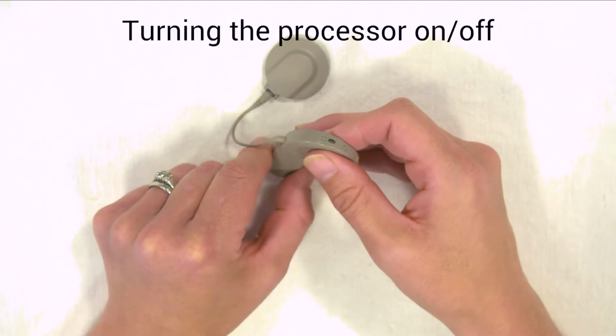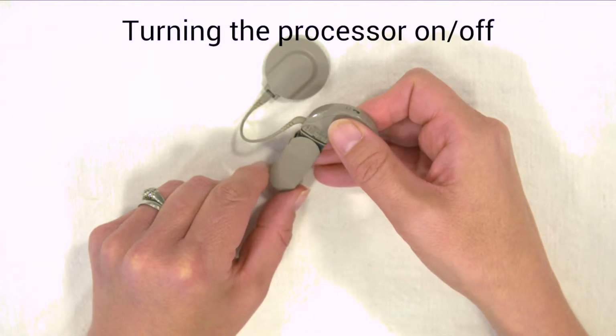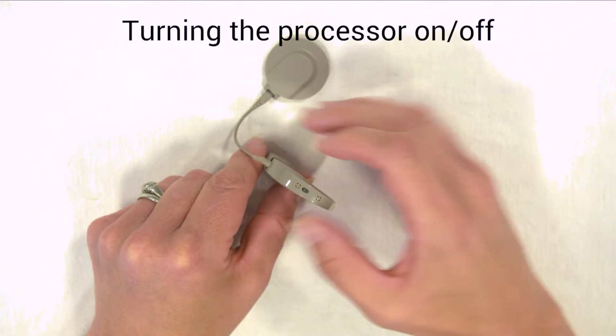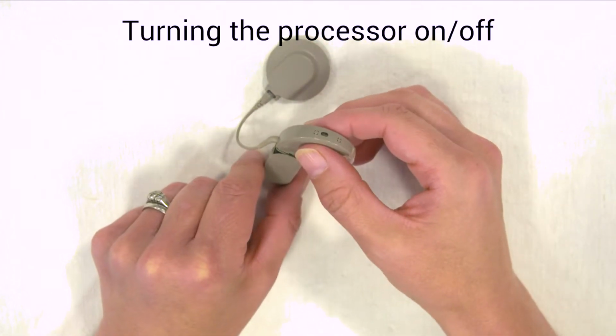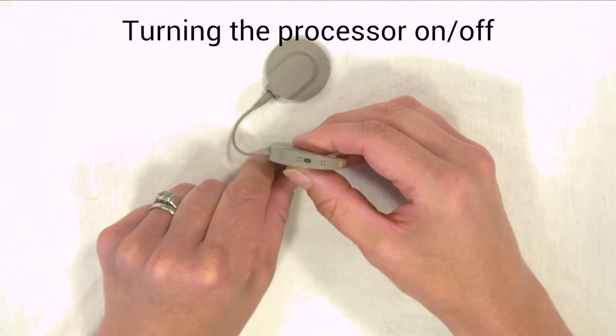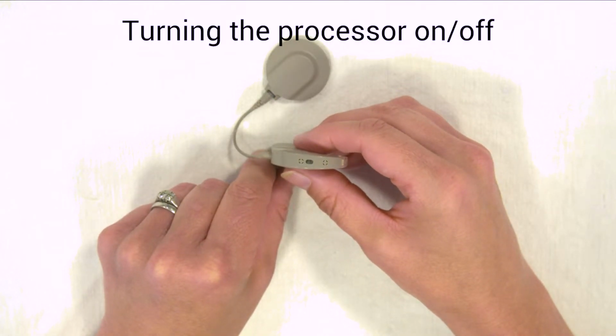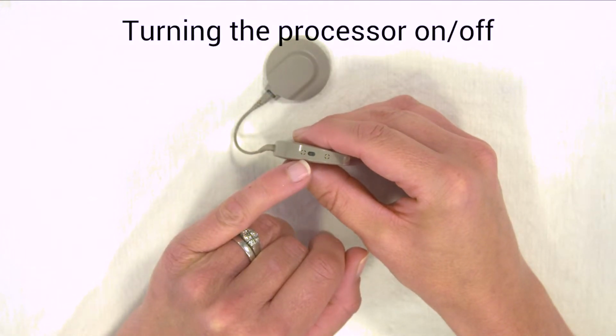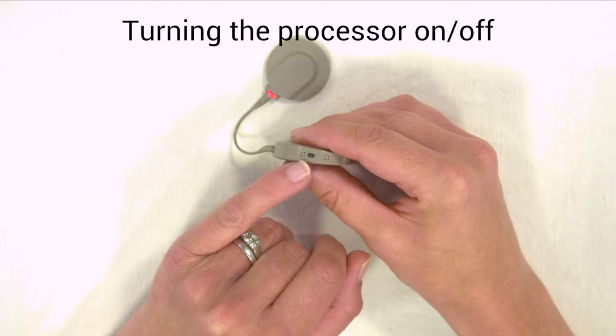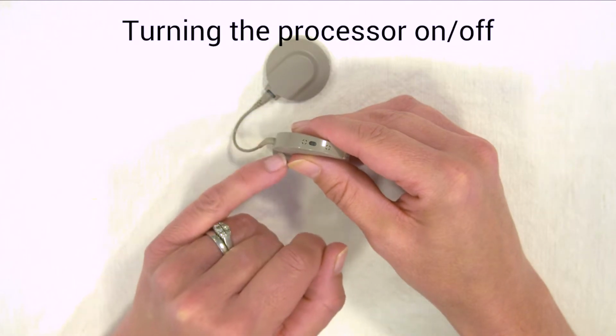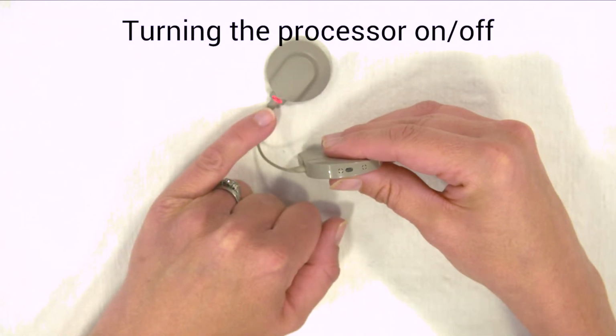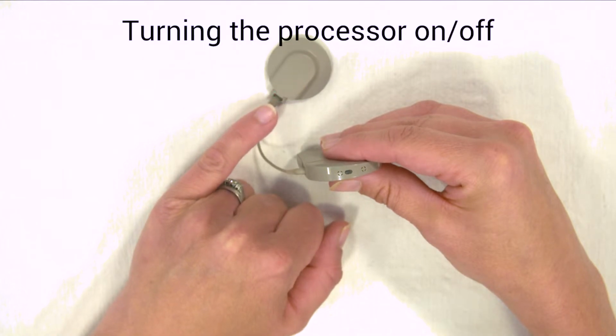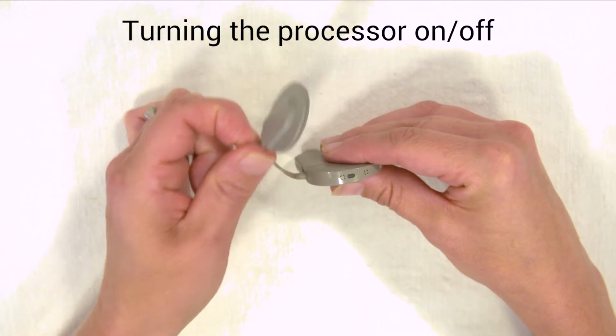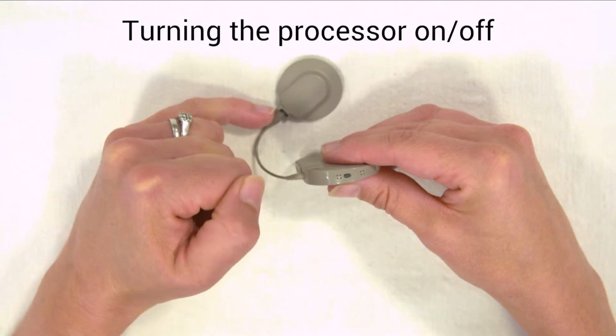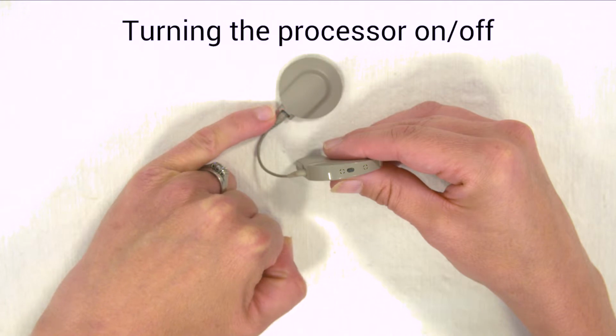To turn the processor on and off, you use the battery compartment. Sliding it off will turn it off, and you can see there's no lights flashing. And when you push it back on, the lights begin to flash. The green flash on here denotes which program you're on. So if you get 4 flashes, you're on program 4. The red light flashing on here will stop flashing once you put the coil onto the patient's head.